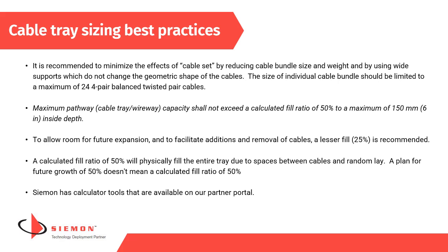The accepted industry calculation for that space between cables is 50%. So when you divide the area of the tray by the area of the cable, you need to take that number and divide it by 2 to get a number that fills the tray to the top. At this point, you can now multiply by the percentage of fill that you have been asked for in the specification or standard. If it's 50%, multiply by 0.5. If it's 40%, multiply by 0.4, and so on.